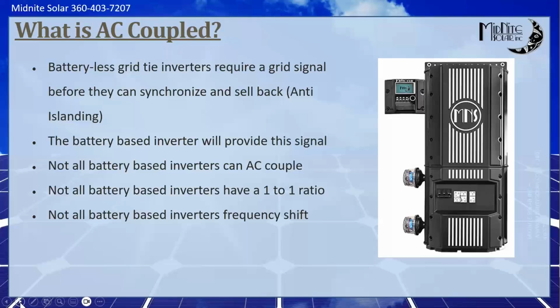And it's also important to note that not all battery-based inverters can AC couple. So it's not just any battery-based inverter that can be driven backwards, which is what you're doing in an AC coupled situation. You're actually driving the inverter backwards in sort of an uncontrolled state, if you will. The control is the batteries absorbing that power. Not all battery-based inverters have a 1-to-1 ratio.